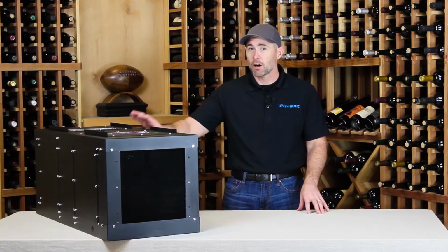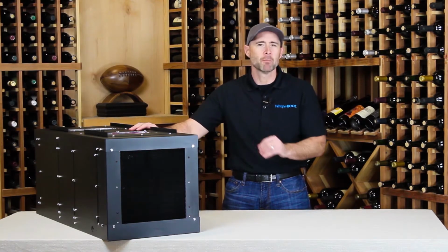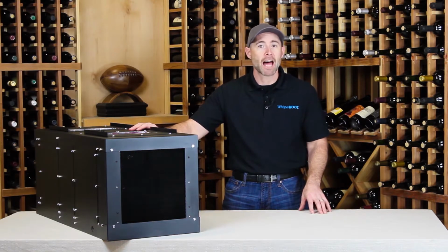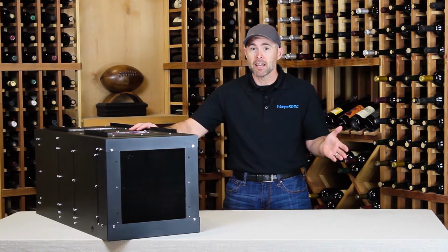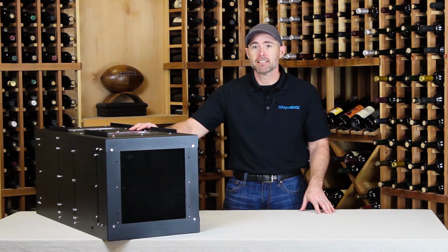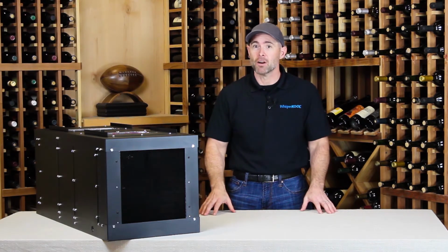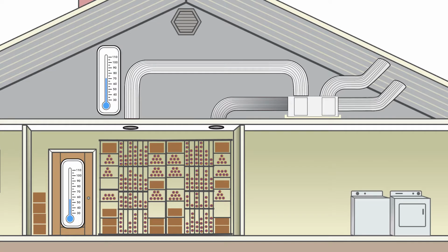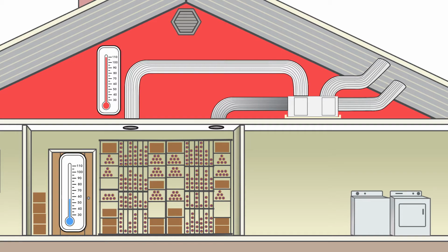The Phantom is a self-contained cooling unit, and that really simplifies the installation. There's no line set between the evaporator and the condenser, so you don't have to have a licensed HVAC technician install it for you, although WhisperKOOL does recommend one. This unit has a 55-degree temperature differential, so the installation environment can be as chilly as 42 degrees or as hot as 110 degrees, and the Phantom will still keep the cellar at 55 degrees.